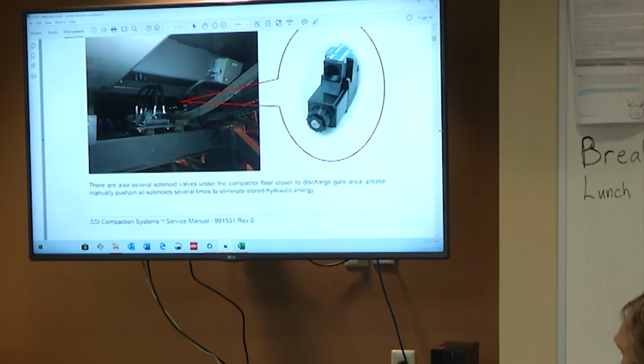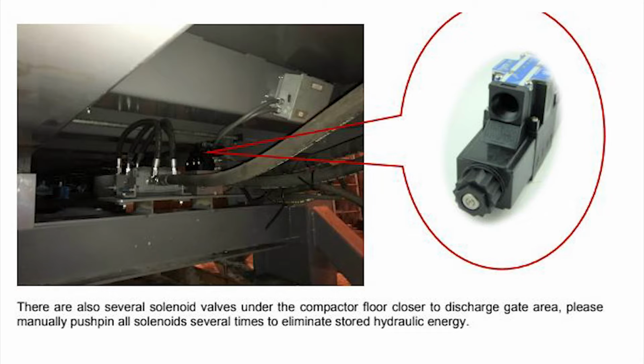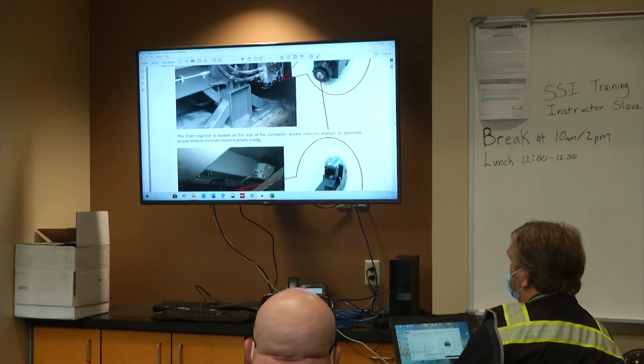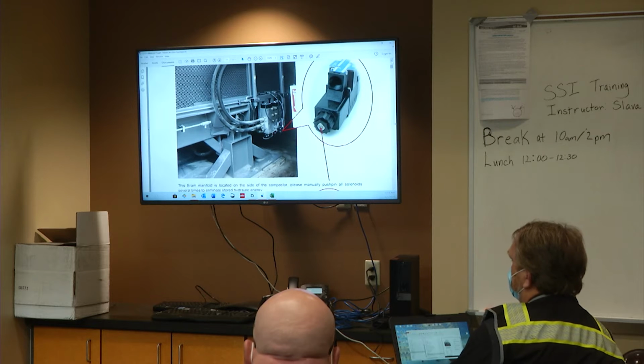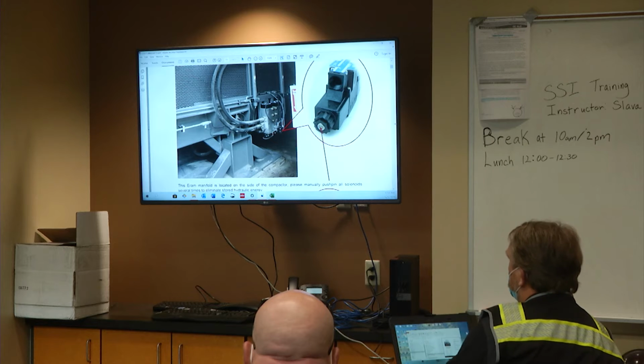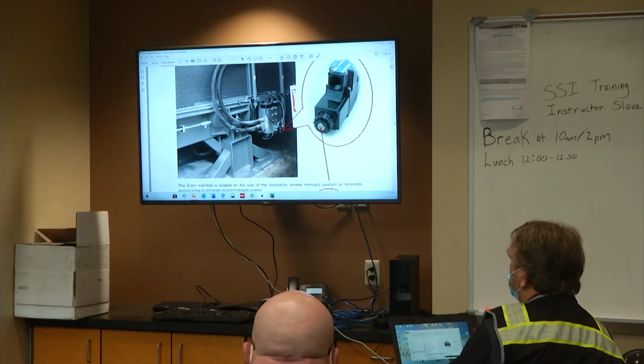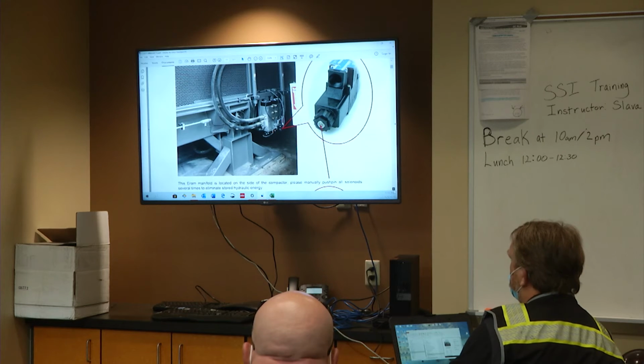There are some here below, but usually if you relieve pressure on the sides, it will cover pretty much the whole system, because most of those connections are very common. They use the same pressure line and a return line. So if you relieve the pressure from one of the logic blocks, it will relieve the whole system pressure.